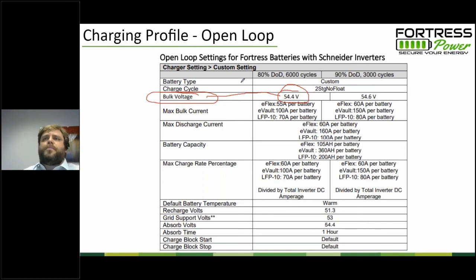But on our website, we have integration guides for each battery and inverter that will tell you the open loop program settings. But the short of it is you're programming the bulk voltage, the absorb voltage, and the float voltage to 54.4, and then disabling float and disabling equalization. You can check what the currents are for the batteries for your maximum charging currents. Another common one is to remember that this is a per battery rating.